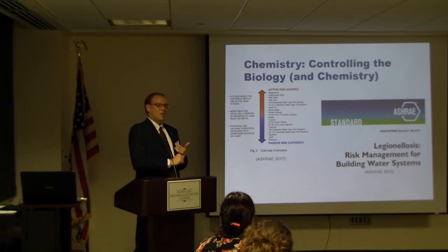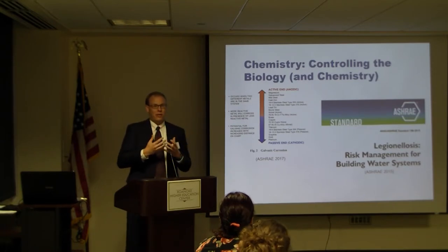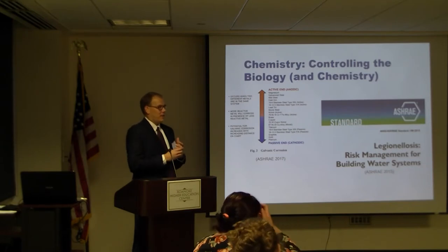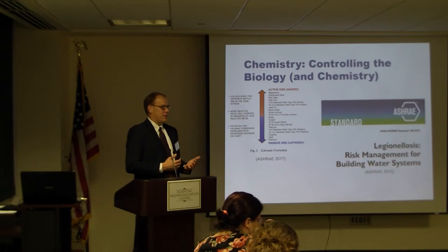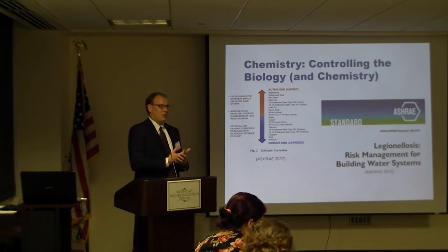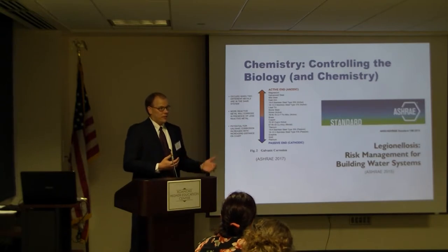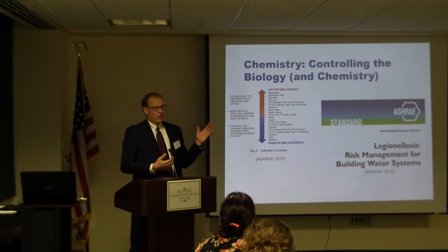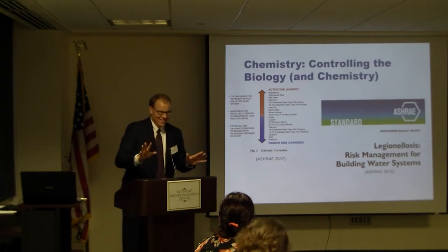If we place cooling towers in a bad spot, so all of a sudden the cooling tower discharges right beside an air intake, all those pathogens that are in the cooling tower air will come right back into the outside air intake. If we haven't managed the biological growth inside of that cooling tower, we're going to have pathogens that spread through the building, and generally those with weak immune systems are most impacted by it. It's called Legionnaires' disease because it started in, I want to say, 1976, Pittsburgh, or in Philadelphia, I think it's Pittsburgh. Philadelphia. Where? Philadelphia. Pennsylvania.